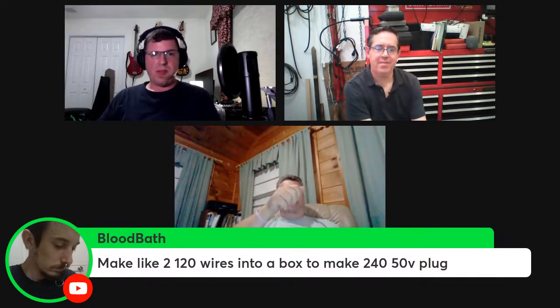Let me ask you this then. If I go into my breaker panel and put in a dual breaker, one line above the other, and it's 240, how do I know it's 180 degrees out? It's because your transformer is center tapped. The way your circuit breaker box is wired, the evens are leg 1, the odds are leg 2. So the double breaker, they're right next to each other for a reason, because you're guaranteed to have different legs, which are 180 degrees out.